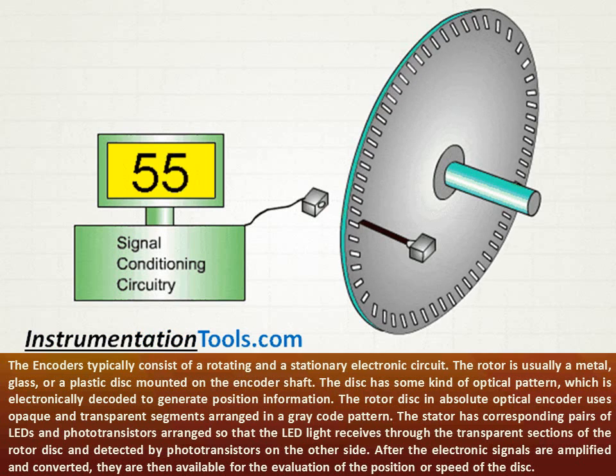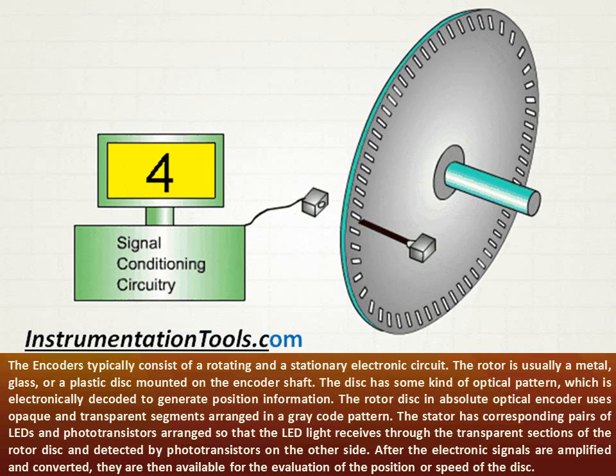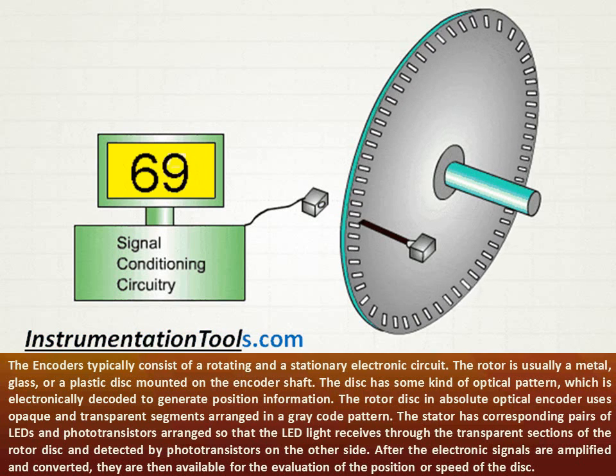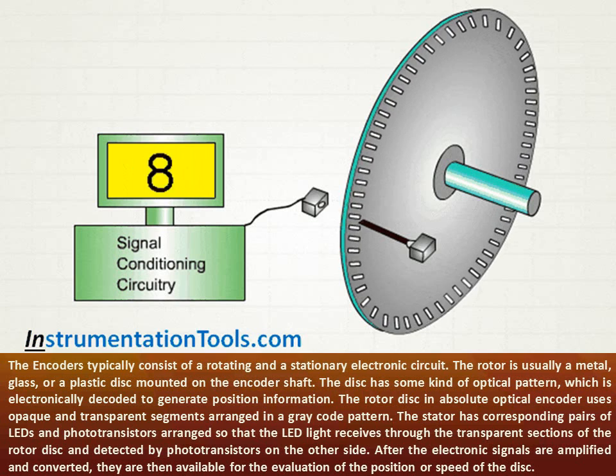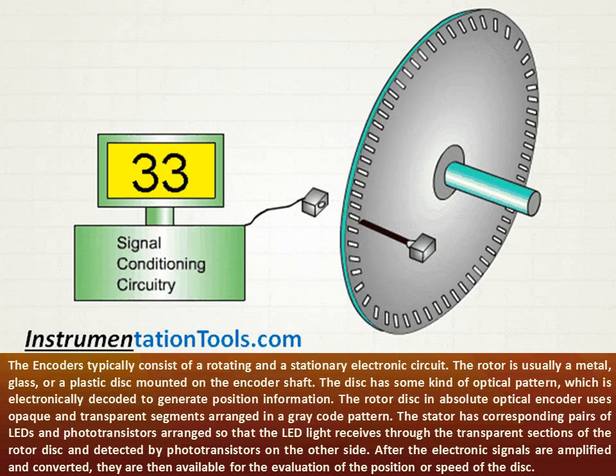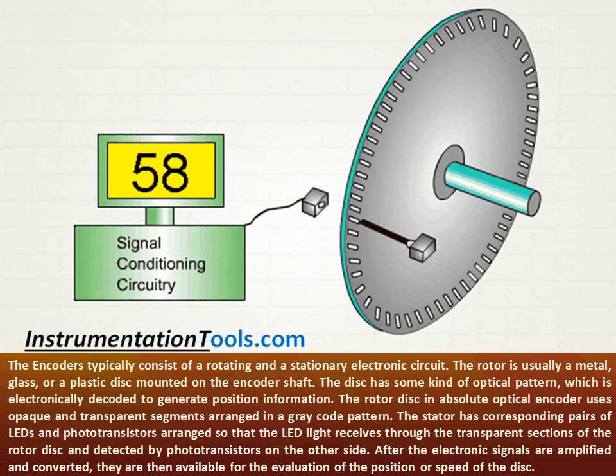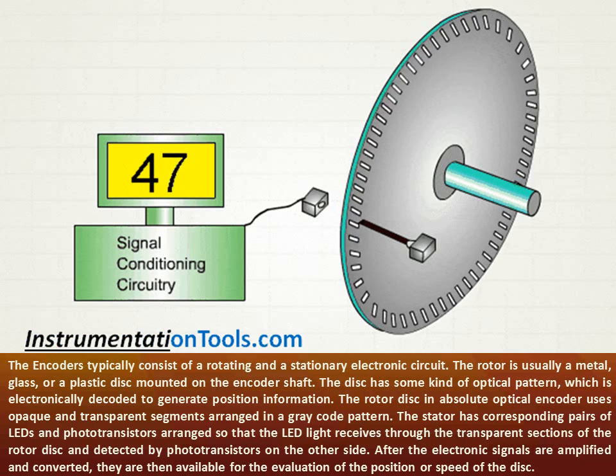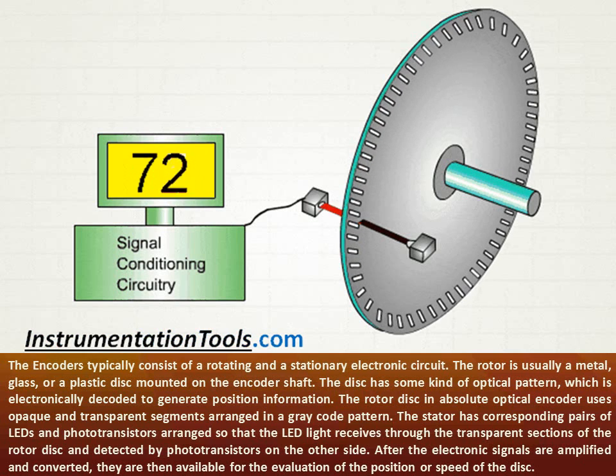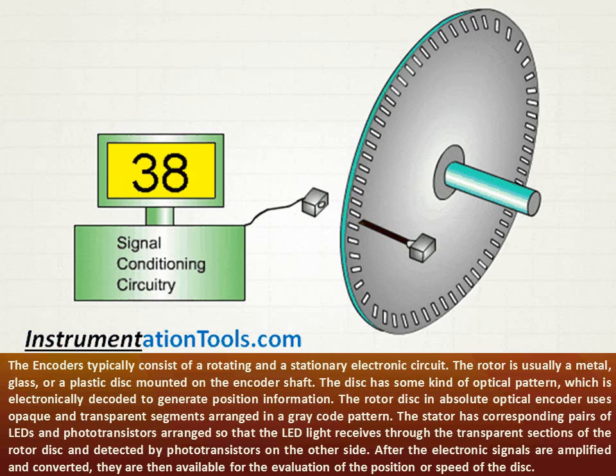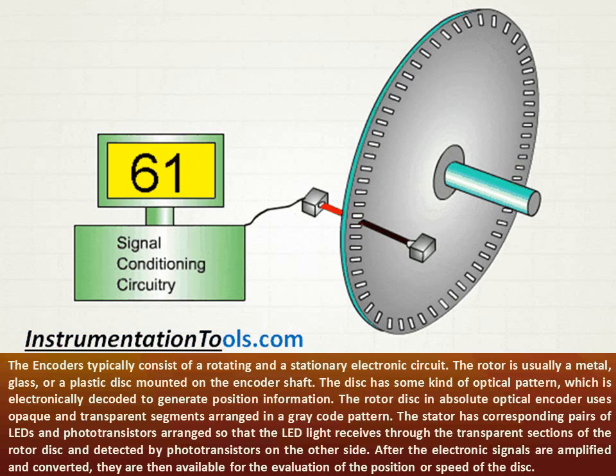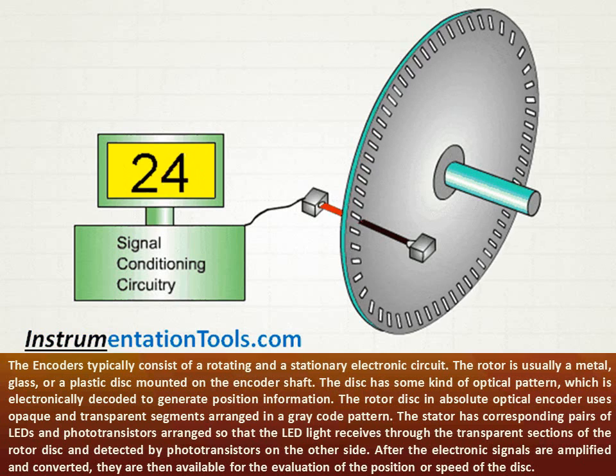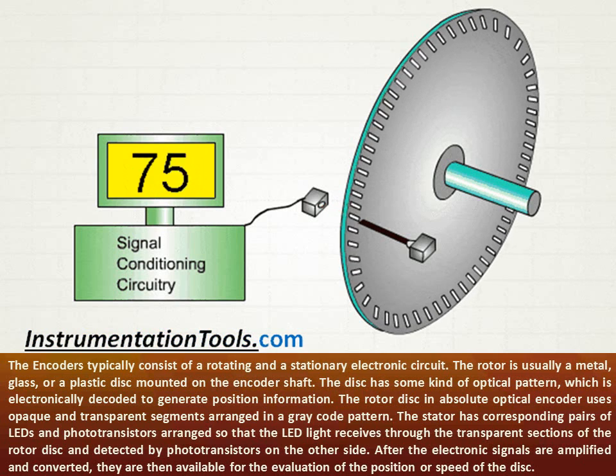The rotor disc in an absolute optical encoder uses opaque and transparent segments arranged in a grey code pattern. The stator has corresponding pairs of LEDs and phototransistors arranged so that the LED light passes through the transparent sections of the rotor disc and is detected by phototransistors on the other side.